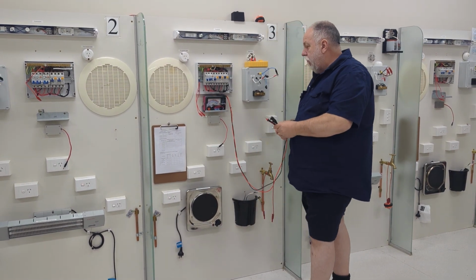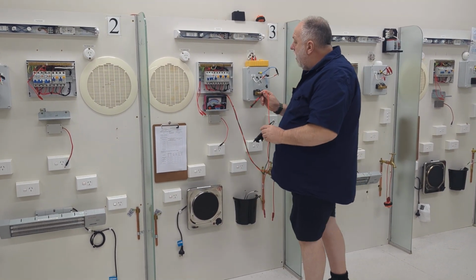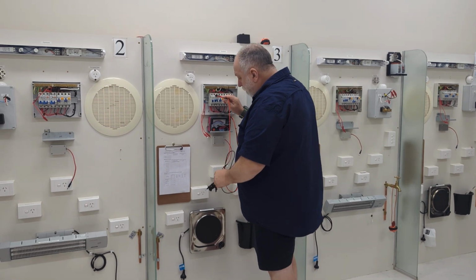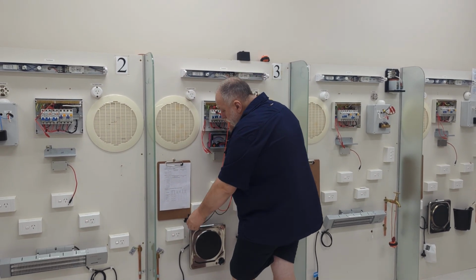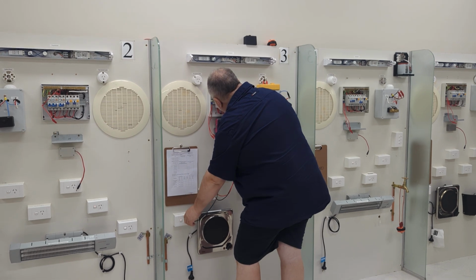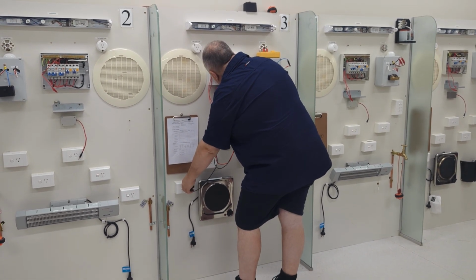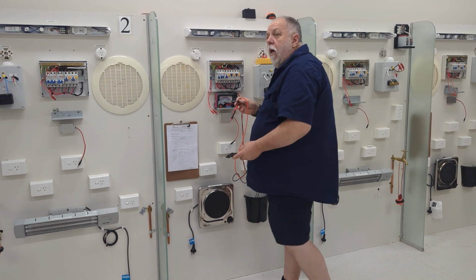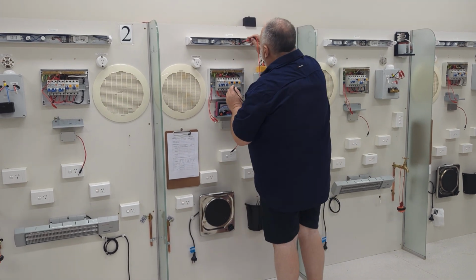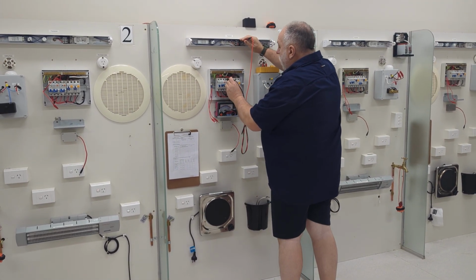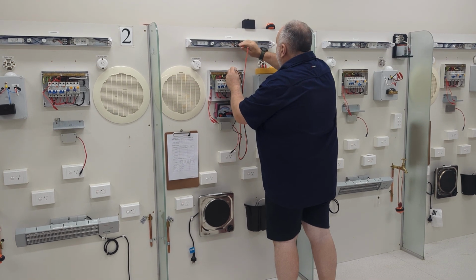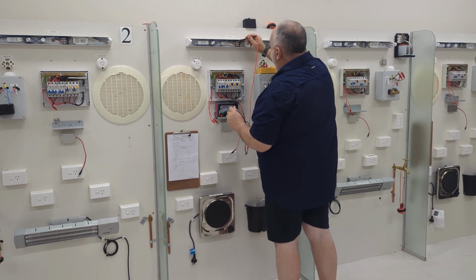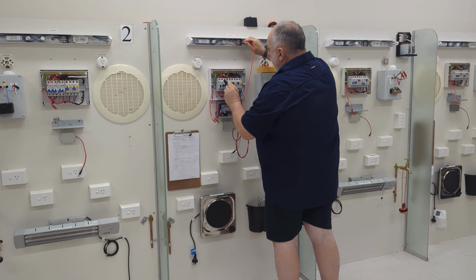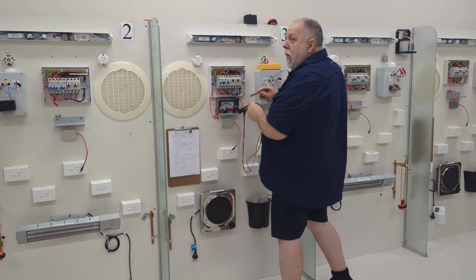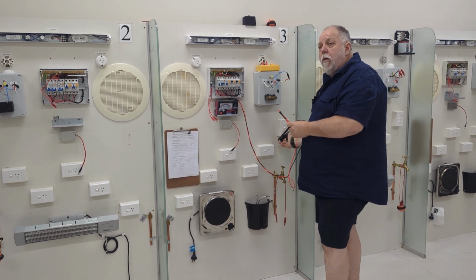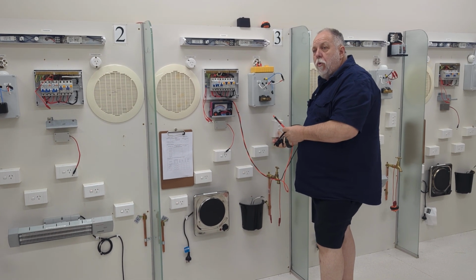Switching of the switches, so checking correct operation. So all I'm going to do is go to my hot plate, still on ohms. Come down to here to my active. Turn the switch on and off. Beautiful. It's switching. And the same when I get to the lighting fluoro here, I'll just turn the fluoro switch off, make sure. And sometimes you might find that it doesn't do anything, which means the fluoro switch is not doing its job, it's not isolating the light. Do you understand what I'm getting at?